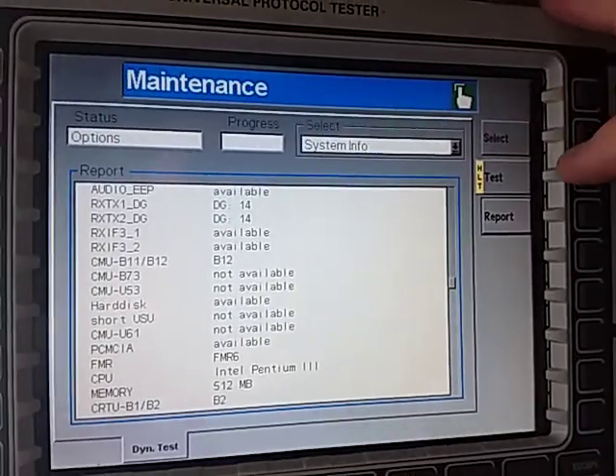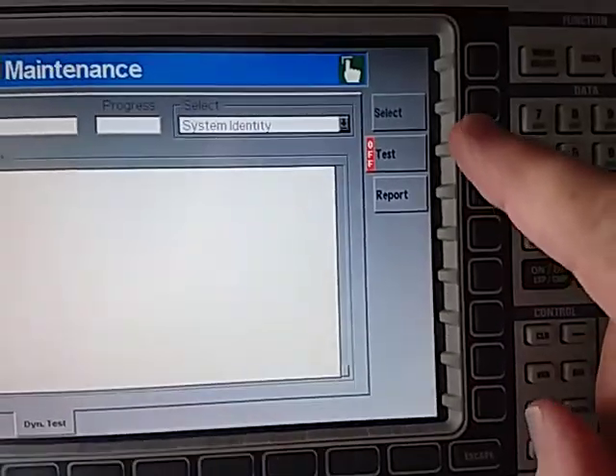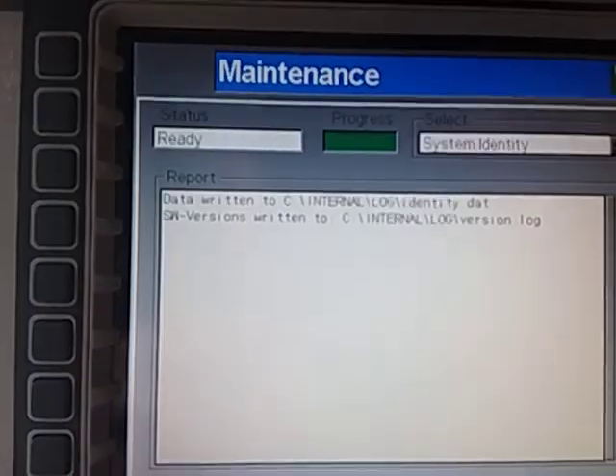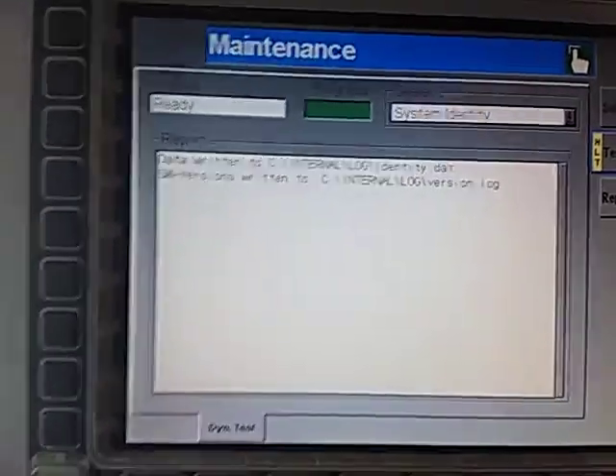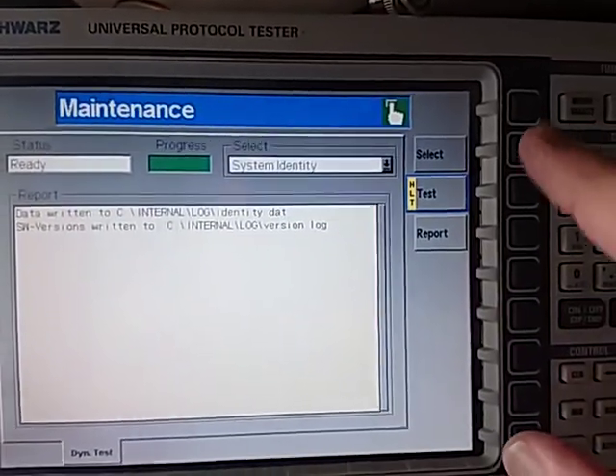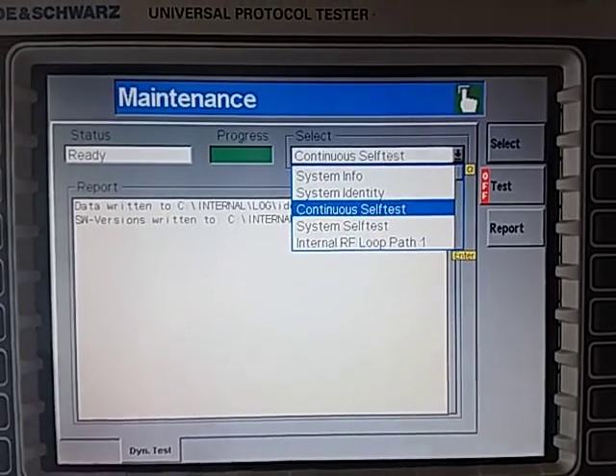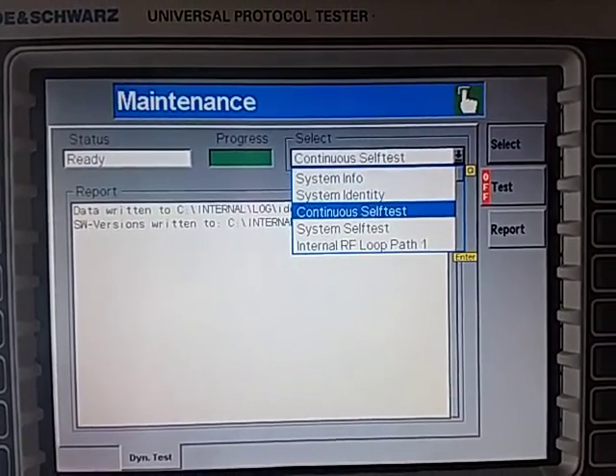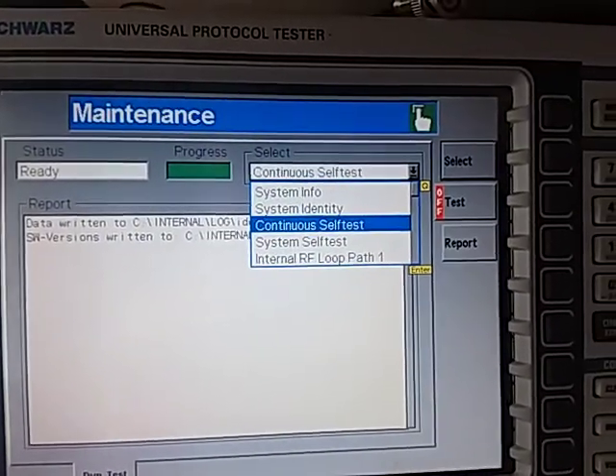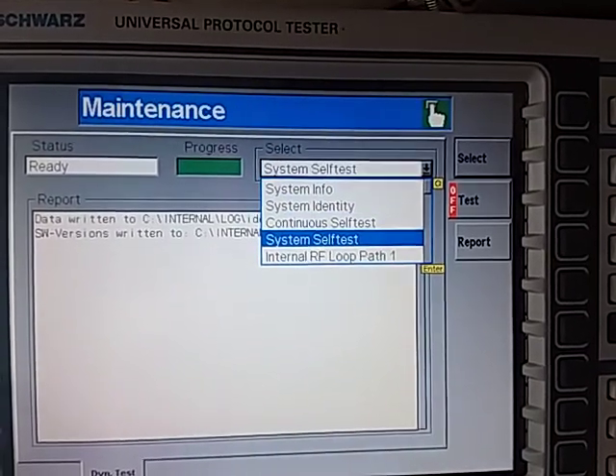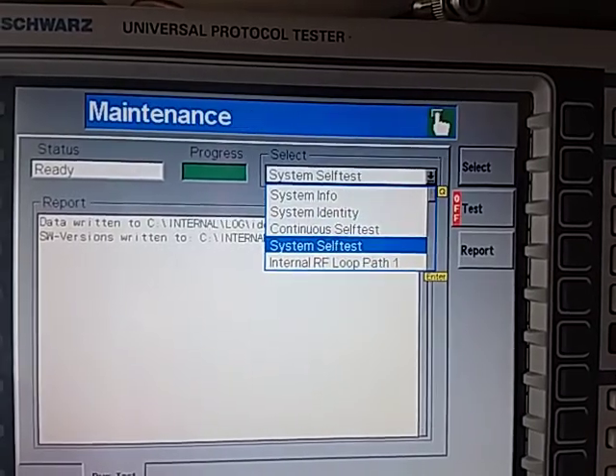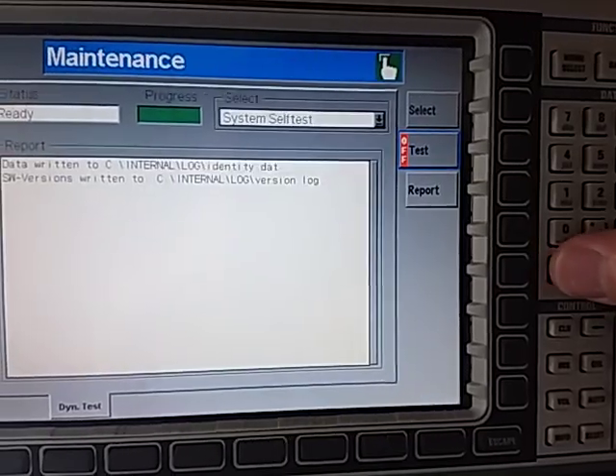The system identity, again we can run this and have a look. All it's going to do is show that a couple of files have been written, and if you go into the file system you can read those two files. It will give you software version and some other bits and pieces that are useful from a servicing point of view. Continuous self-test would be used if you wanted to leave the analyzer running overnight. Maybe yours might be faulting once a week or something like that. Well you could leave it running overnight and this will just run the system self-test continuously.